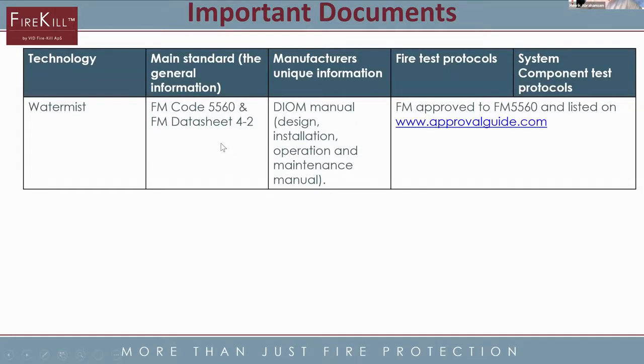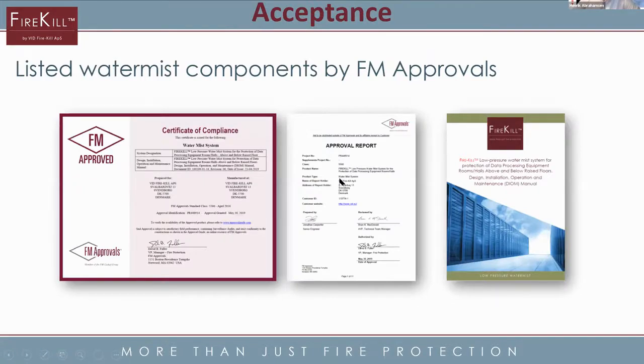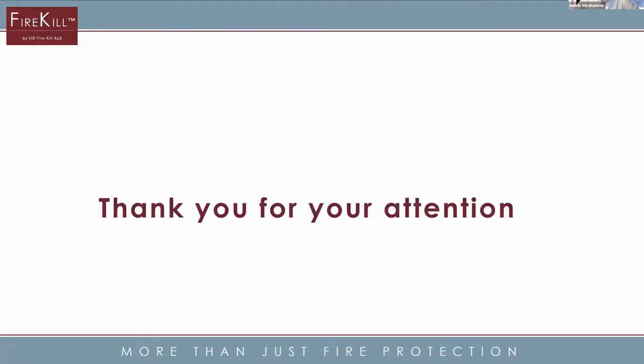The water mist codes for FM include FM Code 5560 and data sheet 4-2. The DIOM is still important to have, because otherwise you cannot install the system — it's different for each manufacturer and has to be FM approved. What you basically need to start installing the system is a certificate, the approval report from FM, and the DIOM from the manufacturer. These are what the manufacturer needs to give to the installer and to the AHJ, and some of it is also relevant for the fitters on site.